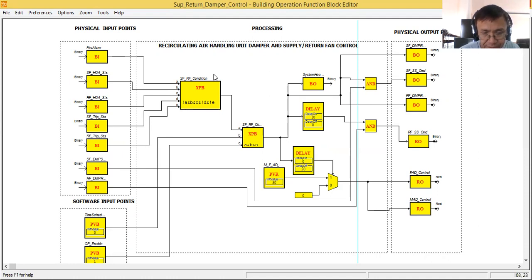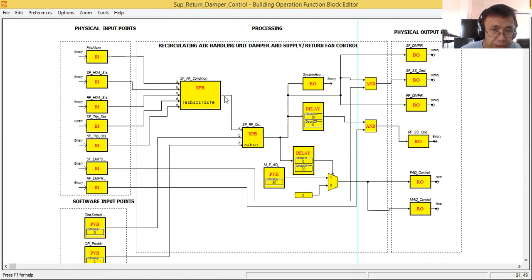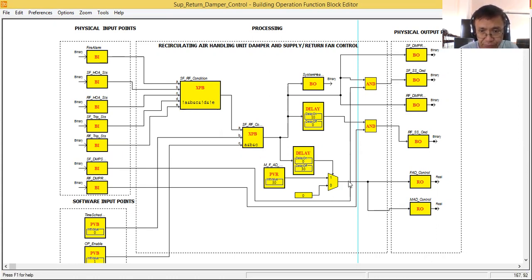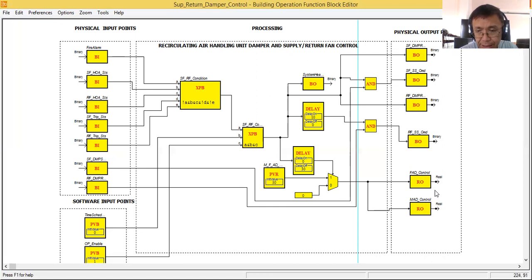As you can see, if you watched my previous tutorial, to start the supply and return fan you have to meet the conditions in these two expression blocks, which I already explained previously. For the fresh air and mixed air damper, using the digital multiplexer, if those conditions are met, there is no on-delay — only an off-delay. Immediately this becomes one, the multiplexer outputs 50%, which is fed to our analog output connected to our IO module. This analog output gives zero to ten volts, so a 50% output gives five volts.